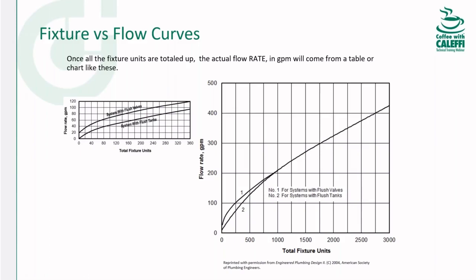And this results in oversizing every time, and you plumbing engineers in the audience know this, because these are outdated. We need more studies on lower flow fixtures that we've developed over the years. These curves are also known as Hunter's curves, because Mr. Hunter developed these many, many years ago, when flows were much higher for fixtures. So these are in dire need of updating. So when we go to pump sizing, we have to be a little bit more careful about this quote unquote design flow that we got out of the fixture unit charts.